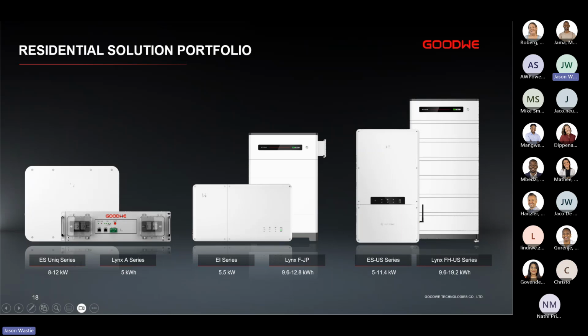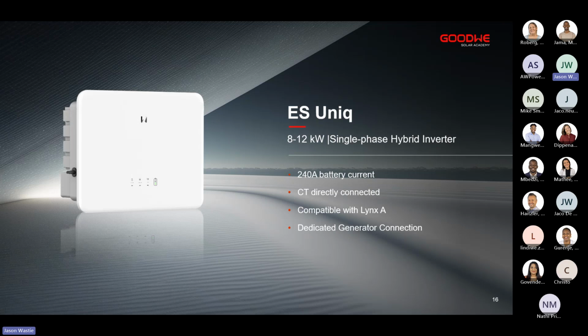Here are a few residential solutions that we have in South Africa. The ES Uniq is a follow-on to our successful ES range, the ESG2. So let's have a look at the ES Uniq. So this is a new range of 3 inverters. It's an 8, 10, or 12 kilowatt model. Depending on the model, it can discharge up to 240 amps of battery current.